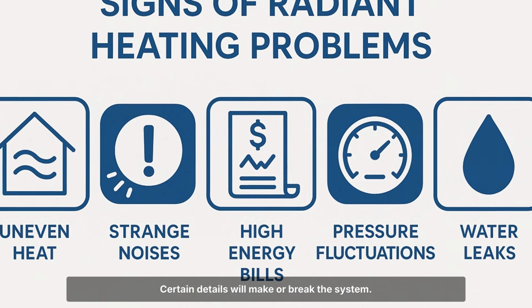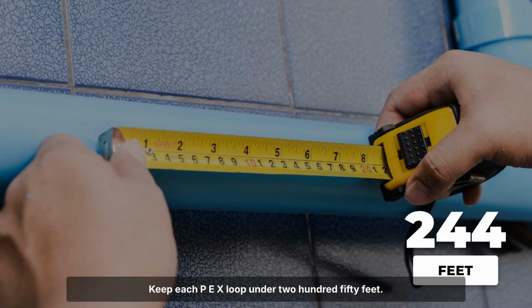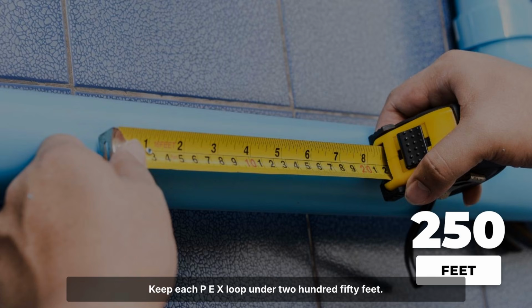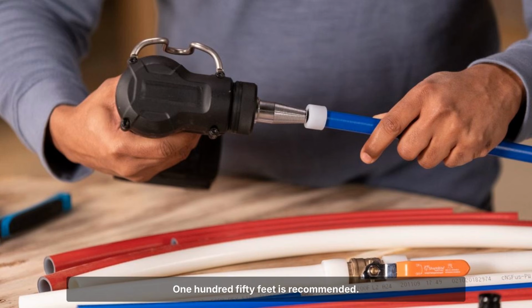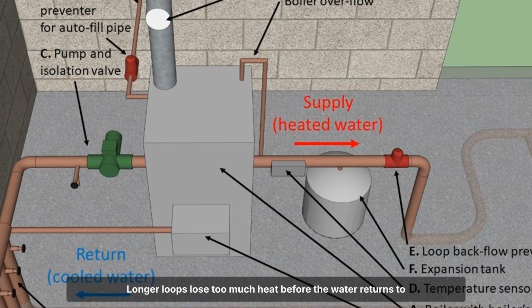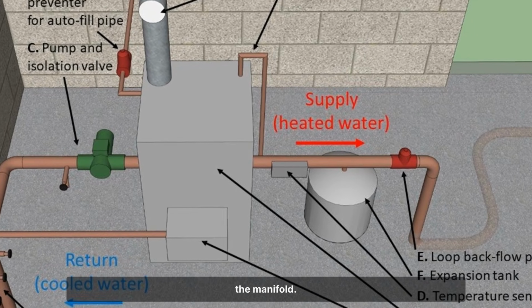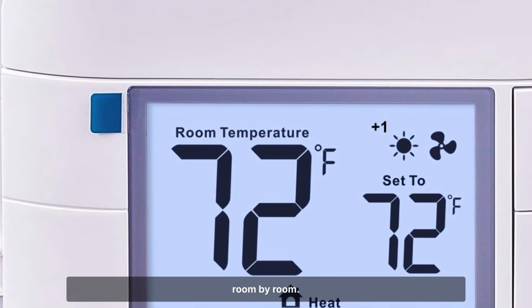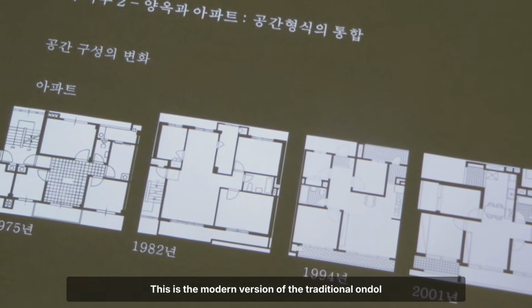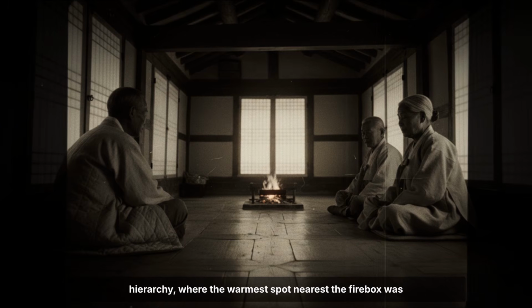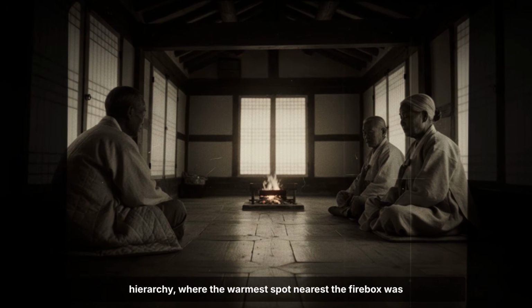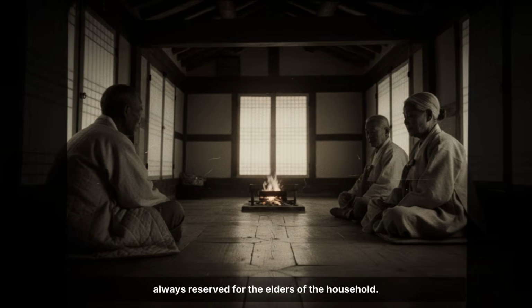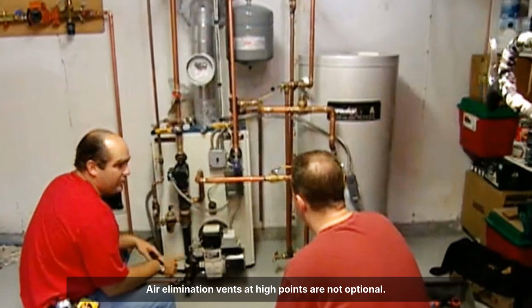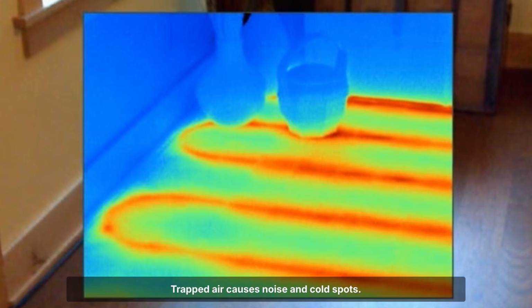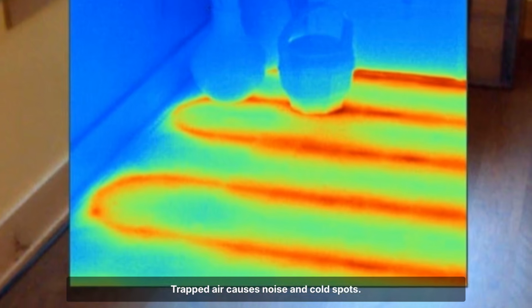Certain details will make or break the system. Keep each PEX loop under 250 feet. 150 feet is recommended. Longer loops lose too much heat before the water returns to the manifold. Install manifolds with zone valves to control temperatures room by room. This is the modern version of the traditional Ondol hierarchy, where the warmest spot nearest the firebox was always reserved for the elders of the household. Air elimination vents at high points are not optional. Trapped air causes noise and cold spots.